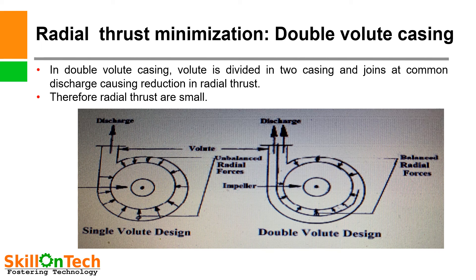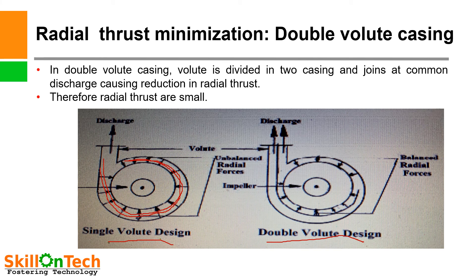Radial thrust minimization: Double volute casing. You can see a picture of a single volute design casing and a double volute design casing. In a single volute design casing, there is area variation in the discharge path, so the pressure also varies, causing production of unbalanced radial forces. These unbalanced radial forces are balanced to a certain extent by modifying the single volute design casing into a double volute design casing.